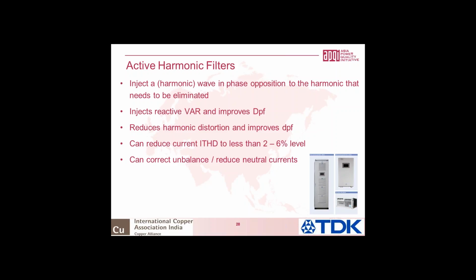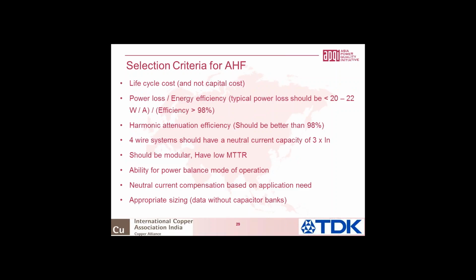I mean, especially if you got a 3-phase 4-wire system, you got excess neutral currents, or all the 3 line currents are not balanced. 10-20% unbalance is okay, but there are installations where unbalance could be as much as 30-40%, where active filters can help you reduce the unbalance. And when you want to select active filters, again, it should be based on life cycle cost, not on capital cost.